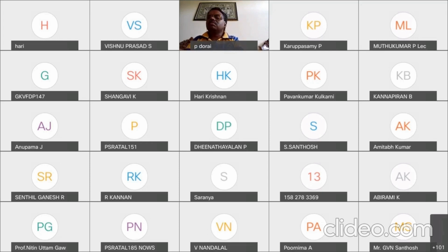And we come to the next, the multi-rate parameters, where we have a temperature thermal sensor and a pulse oximeter used for measuring. Due to COVID, we have individual pulse oximeters, whereas in the bedside monitor inside the ICU, we have ECG parameters, heart rate monitors, as well as the respiratory systems. Everything will be displayed on the display. For the ECG, we use a normal electrode as a sensor, since electrical signals are available in electrical form and can be taken directly with the electrode. As well as the temperature sensor, we use a PT100 to find out the temperature of the body. And the respiratory rate can be derived either from the ECG waveform or from the SpO2.